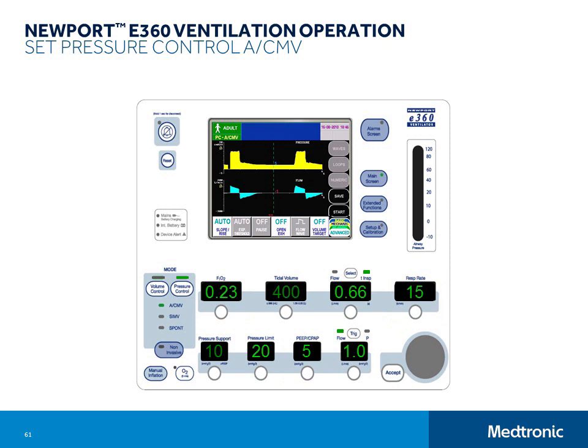On the GUI screen, you will notice that the expiratory threshold is now dim, since there are no spontaneous breaths in ACMV. But slope rise is still active, since this control impacts the rise of pressure during the onset of all pressure breaths, including the mandatory pressure control breaths. Don't forget to check alarm limits after every breath parameter change.